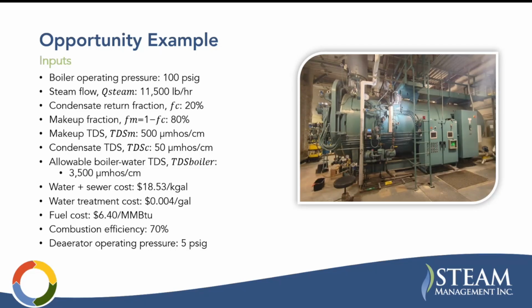Your makeup water, this is a pretty reasonable level on your TDS. This unit is micromhos per centimeter. You also see microsiemens. There are different units for these, but they can all be plugged into the equations that we're going to use as long as you keep your units consistent, because they do cancel out. This is a typical boiler limit for a fire tube boiler, 3,500 micromhos. That equates to around 2,100 parts per million of total dissolved solids.